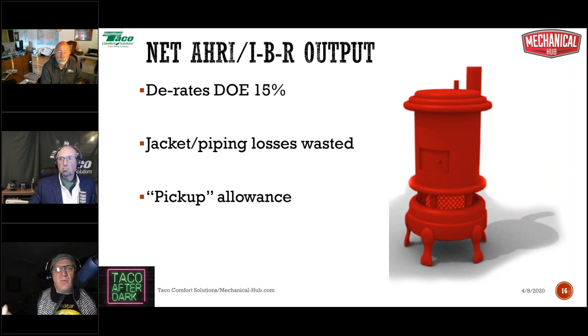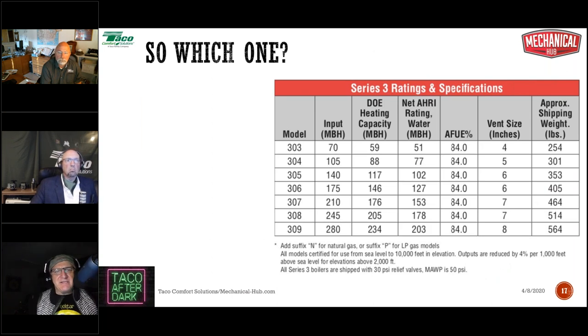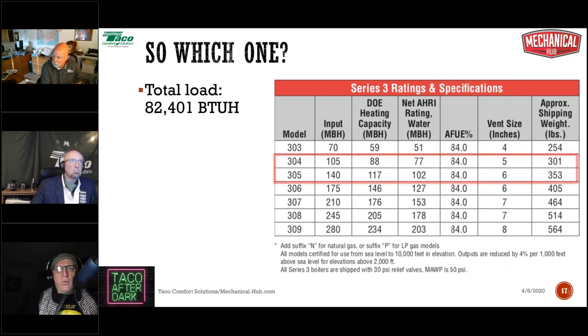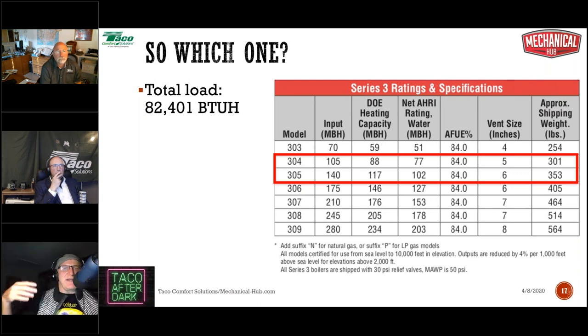So when it comes to which output do I choose to size my boiler, I think the biggest thing is it's going to depend upon where the boiler is going to be installed. To me, if it's in a modern closet or it's surrounded in a finished basement, that sort of thing, I think the DOE rating is perfectly fine. If it's in an unconditioned, unheated basement, all right, and if it's connected to an older system where there's a lot of pipe and it's black iron and everything, then you're going to be looking at the net AHRI or net IBR rating. Knowing the difference between the two may, in some instances, save you a boiler size.